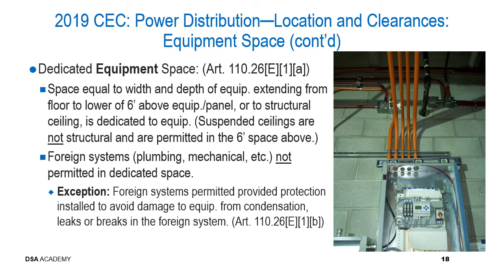Foreign systems, such as plumbing and mechanical, are not permitted in this dedicated equipment space. But there is an exception, of course, in the California Electrical Code. Foreign systems are permitted, provided protection is installed to avoid any damage to the equipment or the panel from condensation, leaks, or breaks in the foreign system itself. And this direction is located in Article 110.26(E)(1)(b).